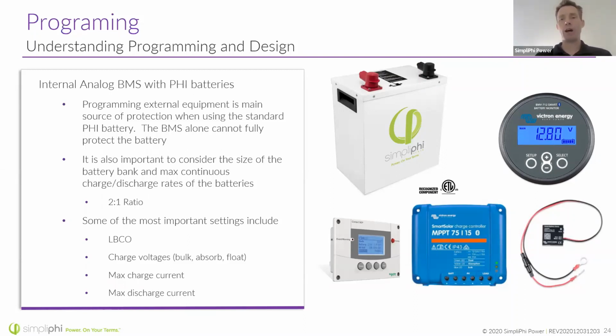What's shown on the screen here is a Phi battery, and that Phi battery has a capacity of 3.8 kilowatt hours. That means the output power that this battery can supply continuously is 1.9 kilowatts. Now, our batteries are all capable of surging, but only for a short time. That Phi battery on the screen, as a 48-volt battery, is rated at 75 amps. C/2 would be half of that, or 37.5 continuous amps. The battery can surge for 10 minutes at 80 amps, but everything should be programmed so that this battery's continuous discharge rate is 37.5.